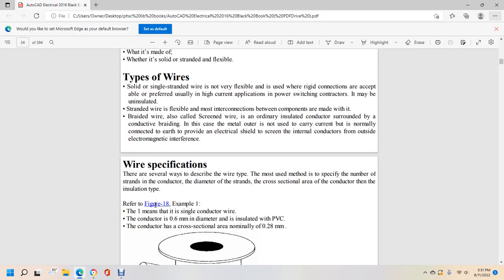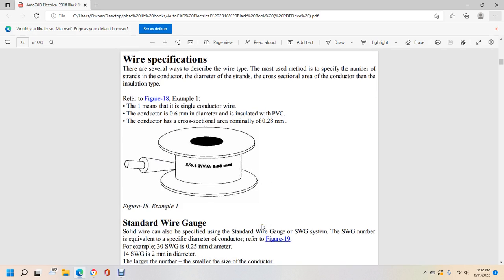Wire specification. There are several ways to describe the wire type. The most common method is to specify the number of strands, the conductor diameter of the strands, or the cross-sectional area of the conductor, and then the insulation type. Refer to figure 18. For example, the 1 means a single conductor wire. The conductor is 0.6 millimeter diameter and is insulated with PVC. The conductor has a nominal cross-sectional area of 0.28 square millimeters, and it shows an example.